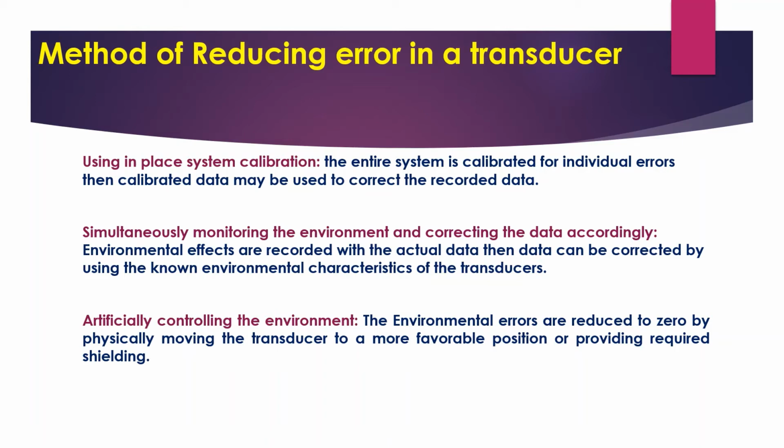Now if that ECG is being carried out for a patient, and the ECG machine is kept near a window air conditioner, the window air conditioner has a compressor and a high magnetic field around it, and sometimes this magnetic field induces voltage into the ECG machine. So unnecessary spikes can appear on the ECG, not because of the patient, but because of the air conditioner present in the nearby environment.